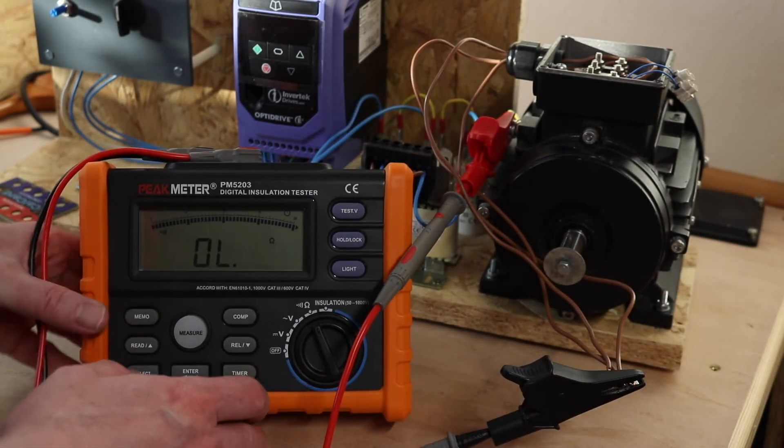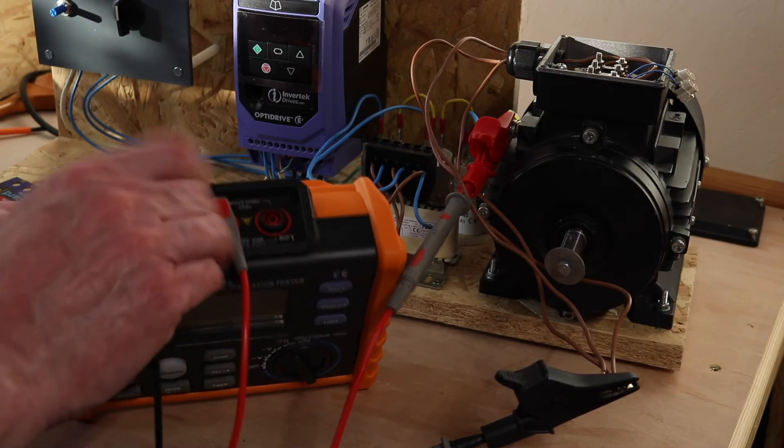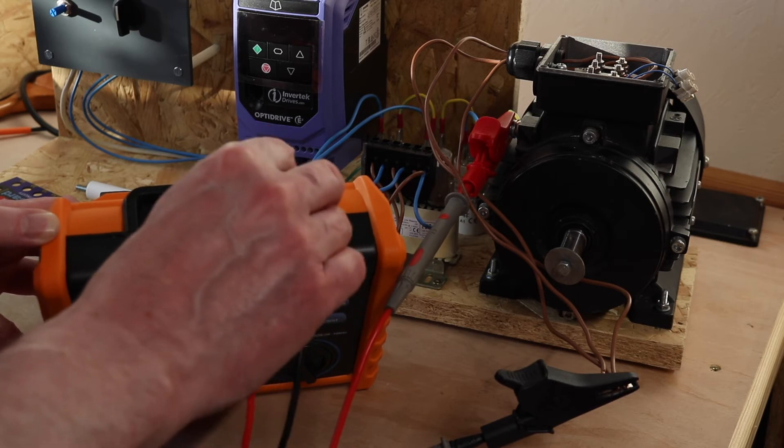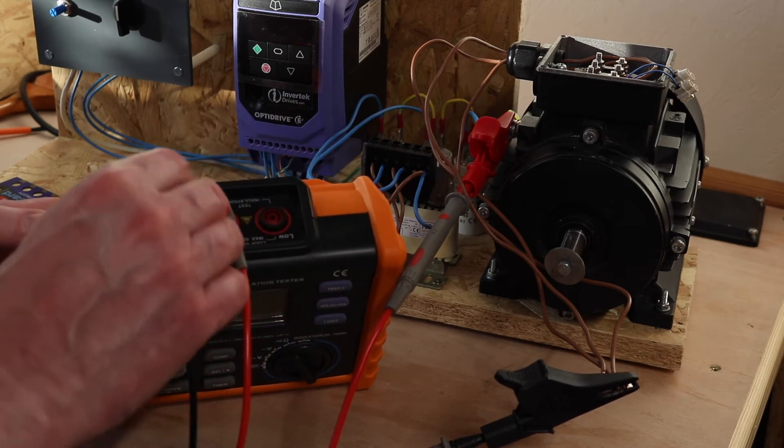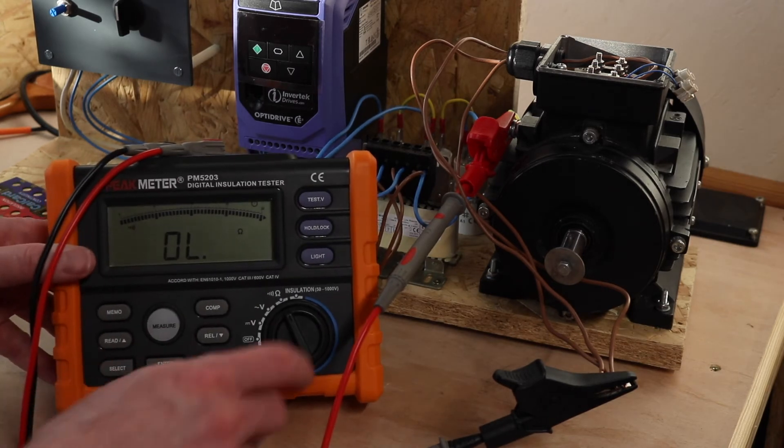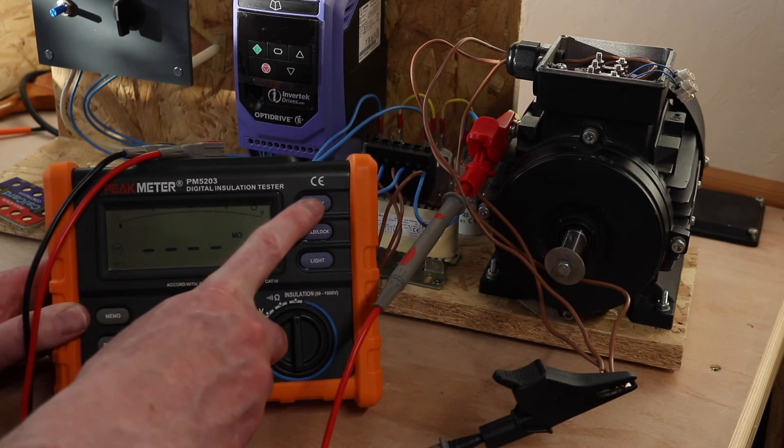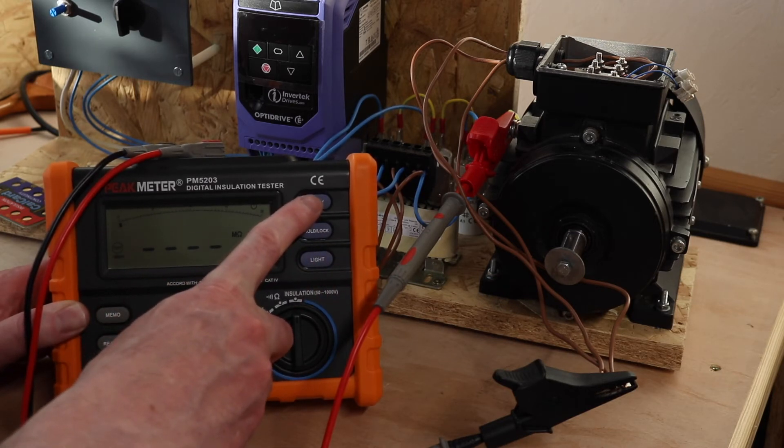For the instrument, I'm going to move the common terminal over to the second insulation test terminal. If you don't do that, you will get a completely open circuit reading, which I'll just show you now. Let's turn it around there.